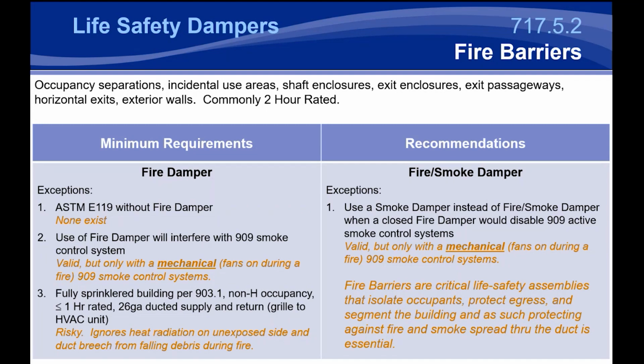There's one thing I do like to bring up with the hourly ratings of barriers versus dampers, and that's that code mandates that any barrier that's rated for 3 hours or more be protected by a minimum of a 3-hour rated damper. And then any barrier that's rated for less than 3 hours can be protected by a damper rated for an hour and a half. This actually can be a bit confusing to some folks because it seems counterintuitive to have a 2-hour rated barrier protected by an hour and a half rated damper, but that's been in the code for quite some time. I don't know the history for that, but it is certainly something that can confuse some folks. Now, using an hour and a half rated damper will also reduce your cost. So it's definitely something that I recommend for your 2-hour or 1-hour rated barriers.